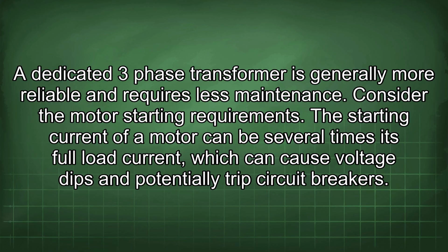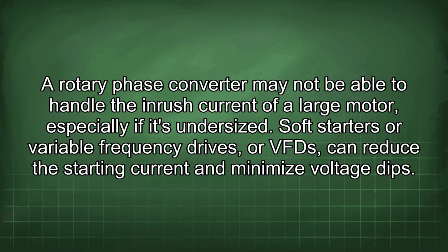Consider the motor starting requirements. The starting current of a motor can be several times its full load current, which can cause voltage dips and potentially trip circuit breakers. A rotary phase converter may not be able to handle the inrush current of a large motor, especially if it's undersized. Soft starters or variable frequency drives, or VFDs, can reduce the starting current and minimize voltage dips.